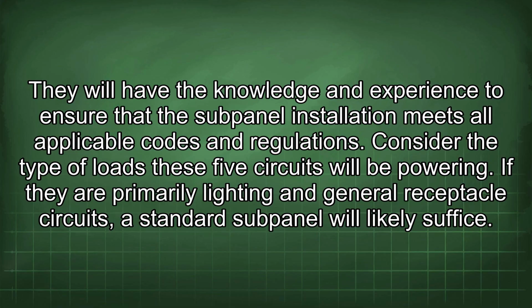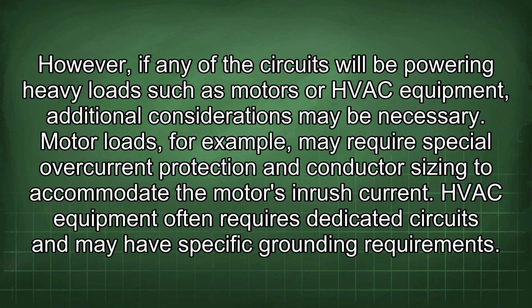Consider the type of loads these 5 circuits will be powering. If they are primarily lighting and general receptacle circuits, a standard subpanel will likely suffice. However, if any of the circuits will be powering heavy loads such as motors or HVAC equipment, additional considerations may be necessary. Motor loads, for example, may require special overcurrent protection and conductor sizing to accommodate the motor's inrush current. HVAC equipment often requires dedicated circuits and may have specific grounding requirements.